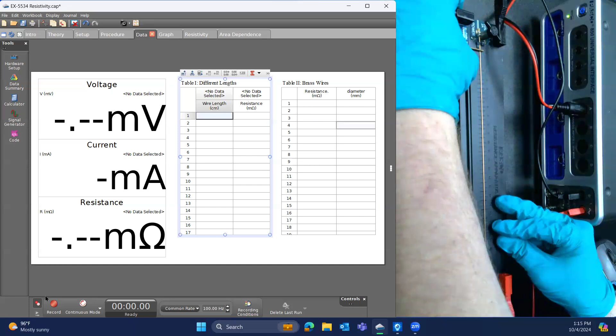Now that we have this physically set up, we need to go back and confirm some settings here. So because this is copper, we want to make sure that we have the voltage gain on the sensor set to 1,000. And the same thing goes for aluminum. So we got to change this to 1,000 and click OK. Once we've done that, we can start collecting data. I'm just going to input, actually, here, we'll start right now.